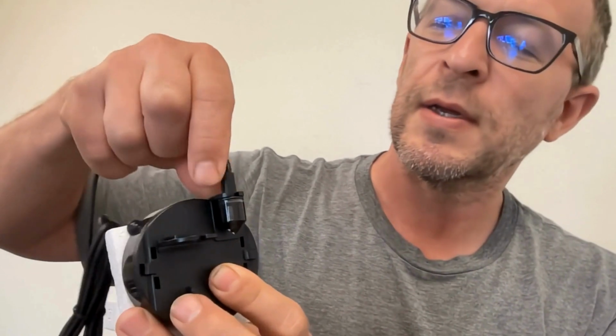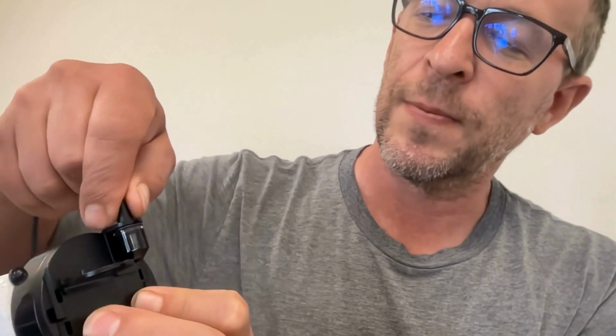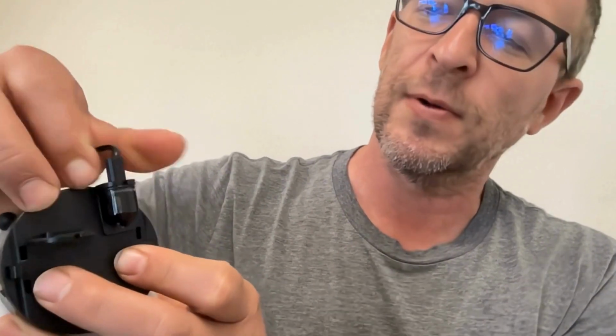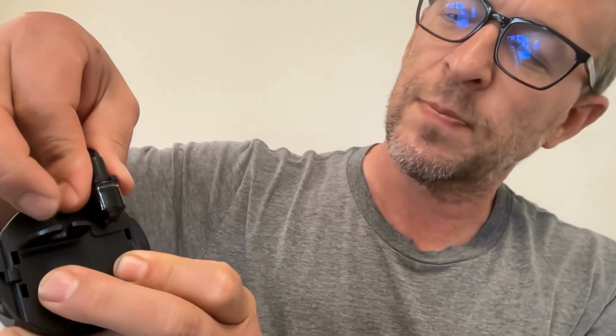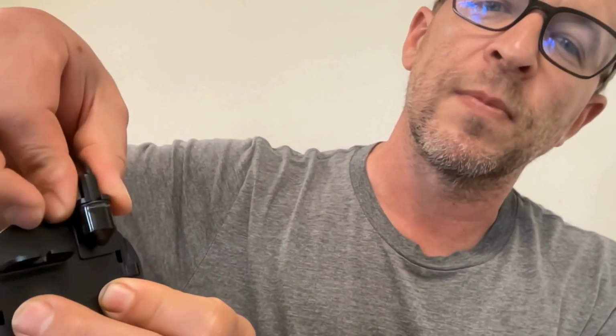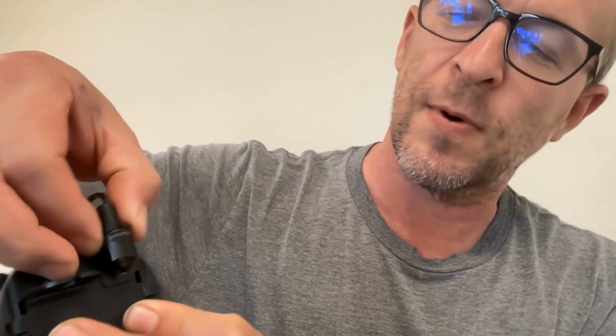Now that does assume that you properly locked in the Optic sensor. The Optic sensor pulls through and then twists. You can see there's a ramp on this side. It slides up that ramp and locks into place. Do not leave that loose or your water level will bounce all over the place because the sensor is free to move and it will move up and down. Also, there's no reason to move the magnet up and down for fine tuning. This piece slides up and down around a 1/2 inch to give you a little bit of fine tuning range, and you can adjust that way.